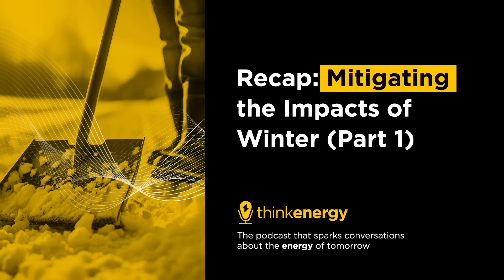Can cold climate heat pumps meet the heating demand on their own, or are there circumstances where backup heat is required? The short answer is it depends. Whether or not you need a backup heat source depends on a number of factors — the type of heat pump you purchase, the climate zone you live in, and the design and efficiency of your home. In some milder parts of Canada, a heat pump might be all you need, but in colder areas, you will most certainly need a backup system, because as the temperature drops, heat pumps become less efficient at heating.